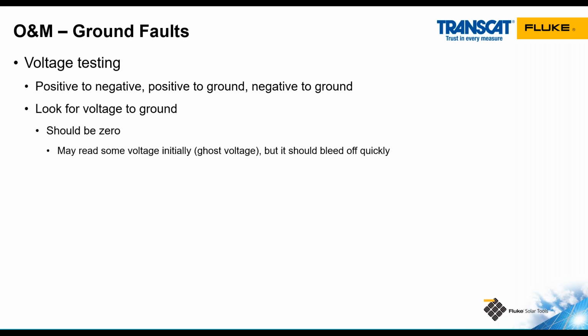There are two ways to find ground faults. The first is voltage testing on my PV source circuits. That's our circuits with strings of modules. I can test from positive to negative and figure out what the open circuit voltage of the string is. And then I can test from positive to ground and negative to ground. In a system that is off with a modern inverter, there should be no connection between the DC side and ground with the inverter off. So when I test between positive and ground or negative to ground, in either case, I should get 0. I may get some voltage that will very quickly bleed off to somewhat close to 0. That's ghost voltage. As long as it's not stable, I know it's not a real voltage there.